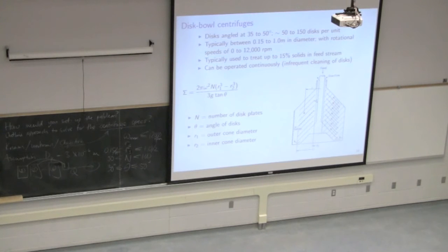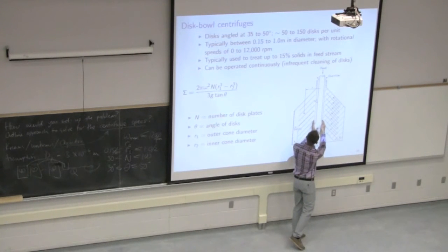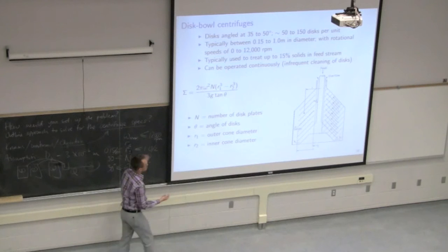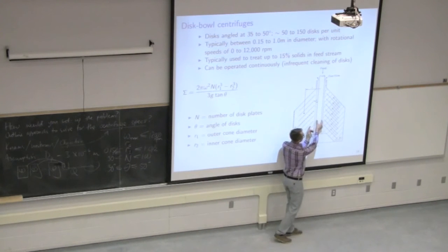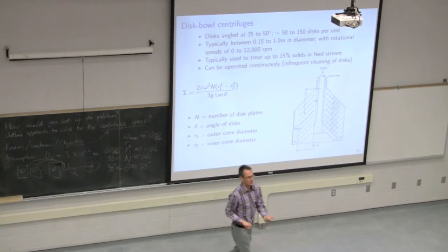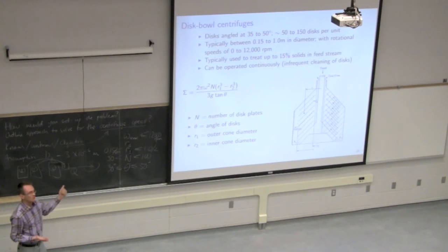But then is there a limit on how small R2 is? Does it have the same limit? There isn't too much of a detail, but obviously there would need to be. If R1 is 15 centimeters, you'd need enough distance for the plates, maybe about 2-3 centimeters. But this is where you start to iterate with the vendor and use their catalog or website to specify this. I don't have a constraint on R1 or R2 on the slides, but the vendor likely will have constraints as well.